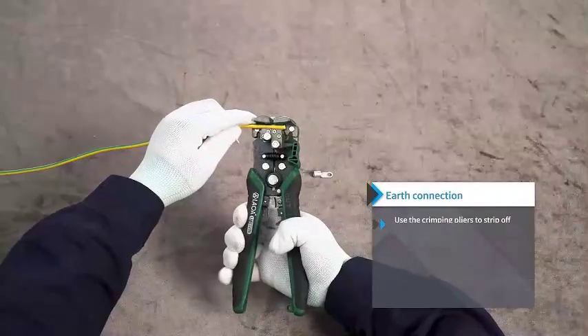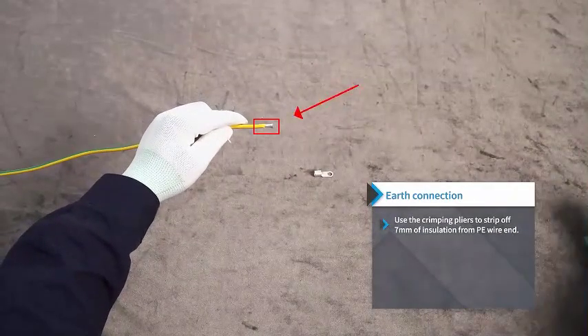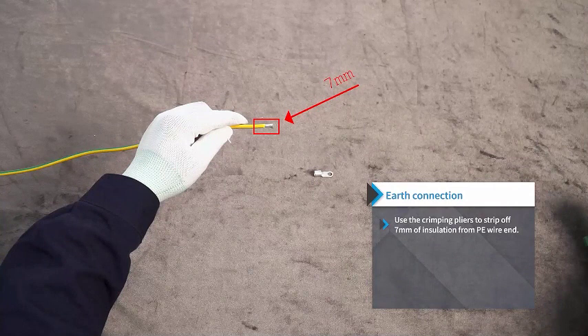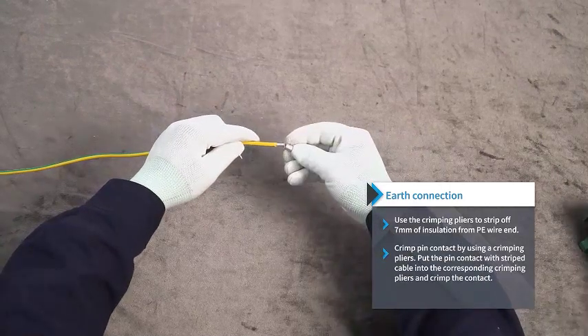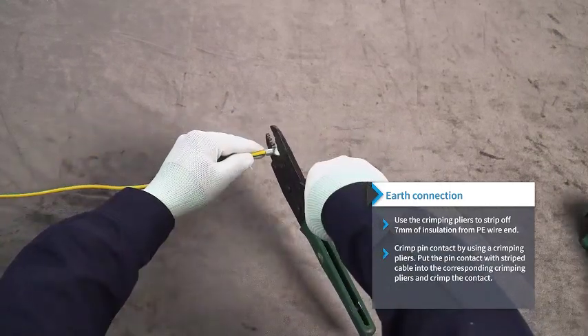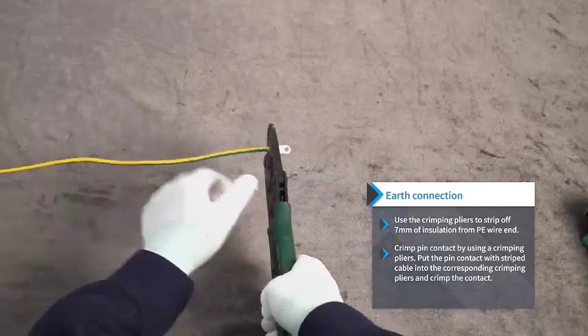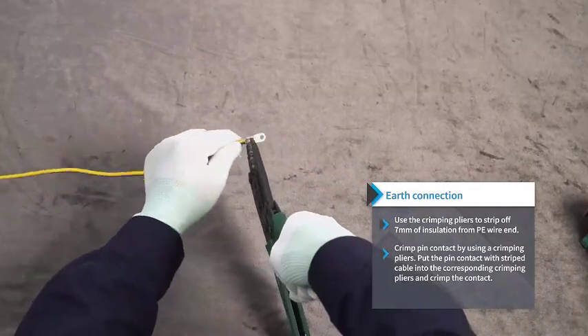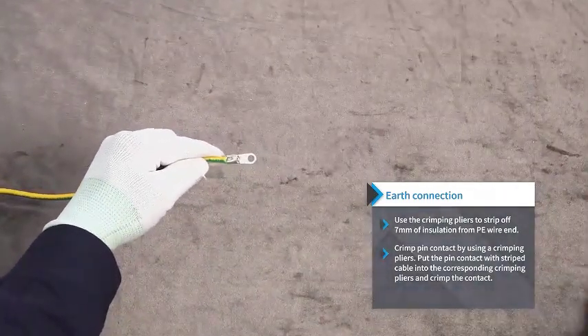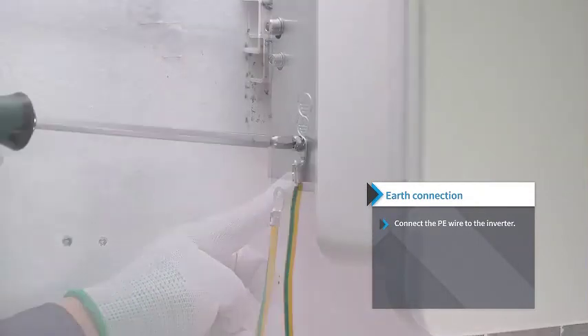Earth connection. Use the crimping pliers to strip off 7 mm of insulation from the PE wire end. Crimp the pin contact using crimping pliers. Put the pin contact with the stripped cable into the corresponding crimping pliers and crimp the contact. Connect the PE wire to the inverter.